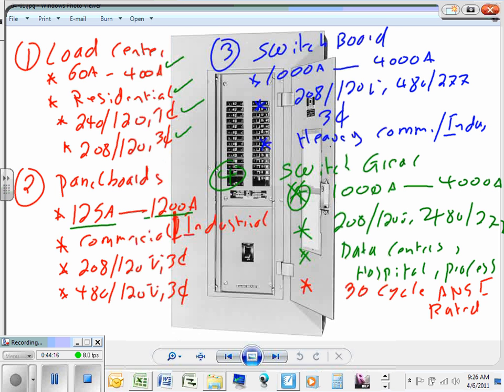Panel boards, guys, the way I personally understand the panel boards, they need a wall to mount them against. That's what a panel board is. It really needs a wall to throw that panel board against. So between roughly 125 to 1200 amp, you can buy a panel. It looks like that. These racks there, throw them against the wall, right? And it has bigger circuit breakers. With 1200 amp, you can have a 500 amp feeder from it. So 125 all the way to 1200 amp.